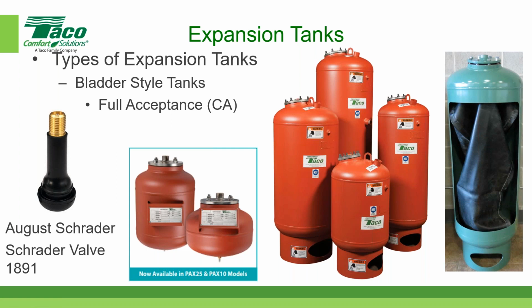So when the bladder style expansion tank that's been pressurized in the air side to 12 pounds gets to the job site, you should be able to use a pressure gauge and put it on the Schrader valve, and you should be able to read 12 pounds. Can I try that in English words, Brett? Yeah, you might want to. If you do not read 12 pounds, that means someone has either let the air out or there's a leak.